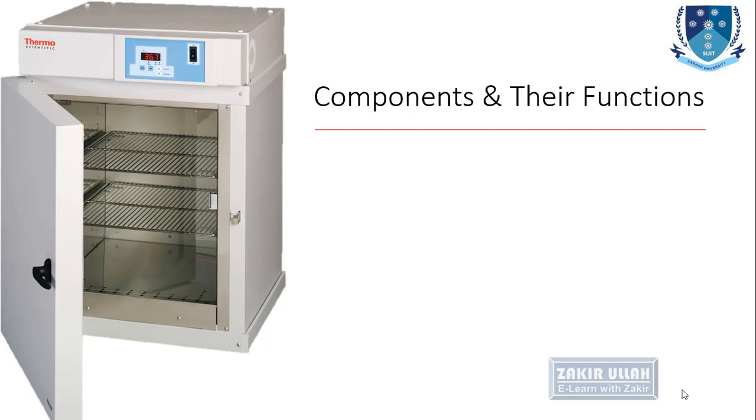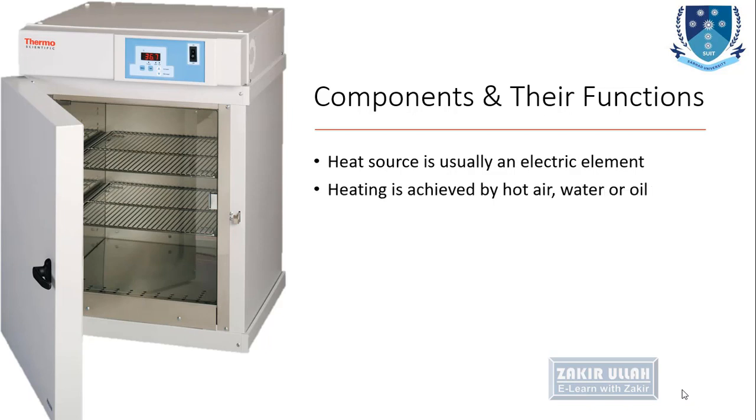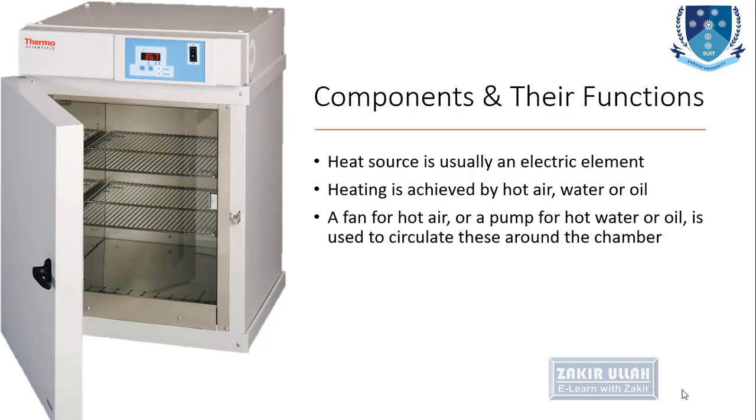Components and functions which are present inside the incubation chambers. The heat source is usually an electric element. Inside the incubation chamber, the heating is achieved by hot air, hot water or hot oil. A fan for hot air is present inside the incubator, or for hot water or oil usually a pump is present, and it is circulated throughout the chamber by this fan or this pump.